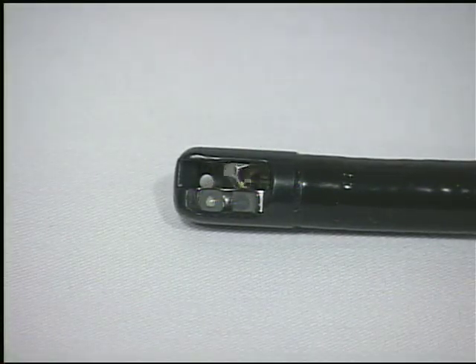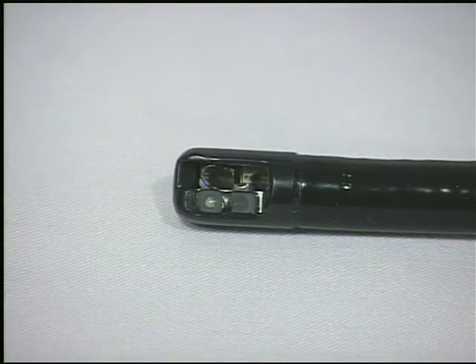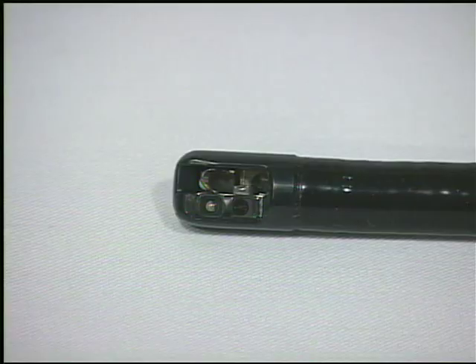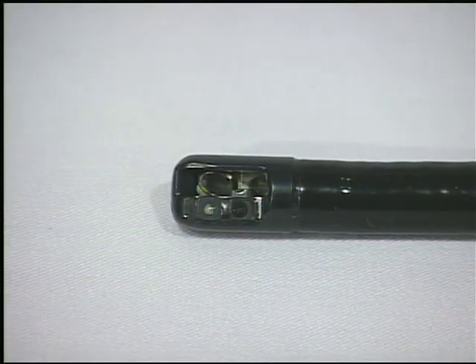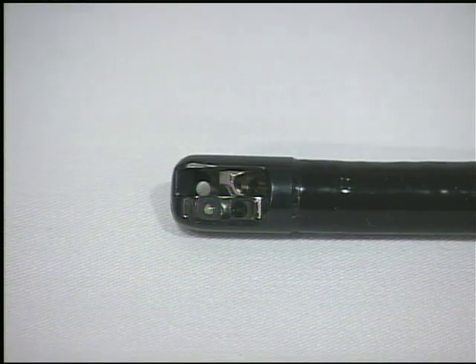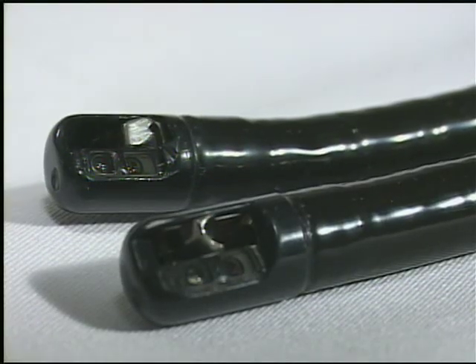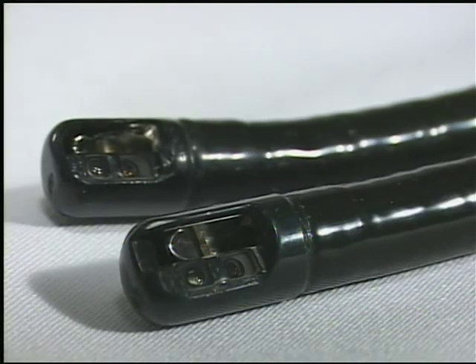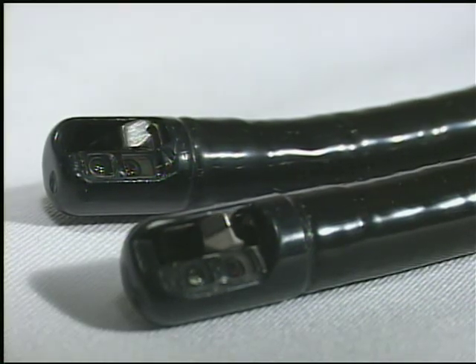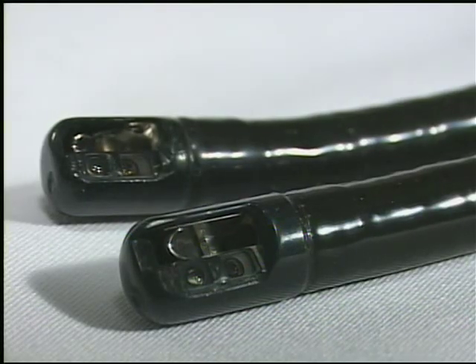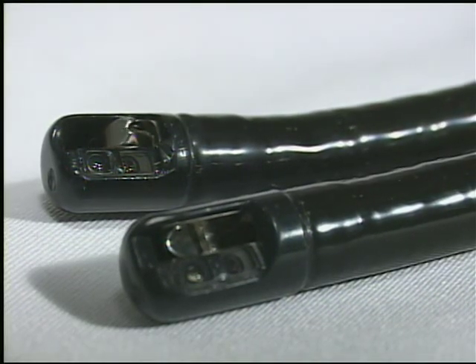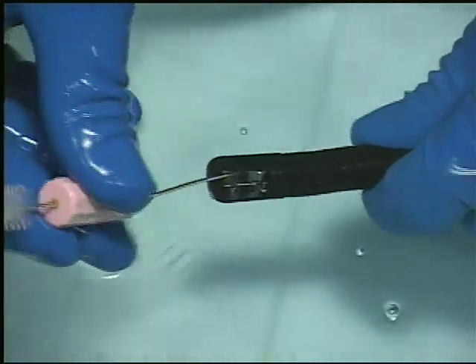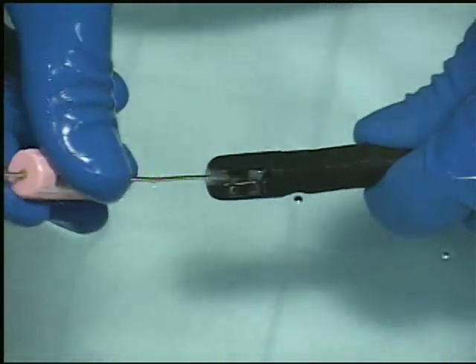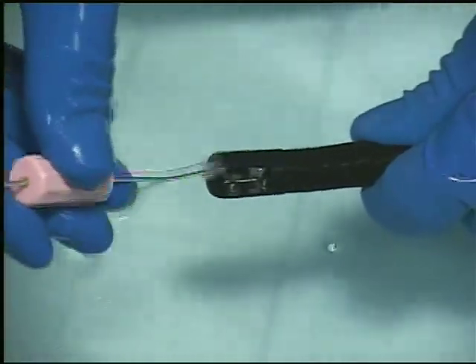Pentax 7070K series duodenoscopes eliminate the need to reprocess this internal channel area because its control wire is completely sealed and never exposed to potentially infectious patient material. A comparison of these two designs reveals an exposed control wire on older instruments. On current generation Pentax duodenoscopes, one cannot see a control wire because it is completely sealed within the scope tip. However, it is still very important that the distal end of the duodenoscope, especially the actual elevator mechanism and area surrounding it, be properly cleaned and reprocessed.